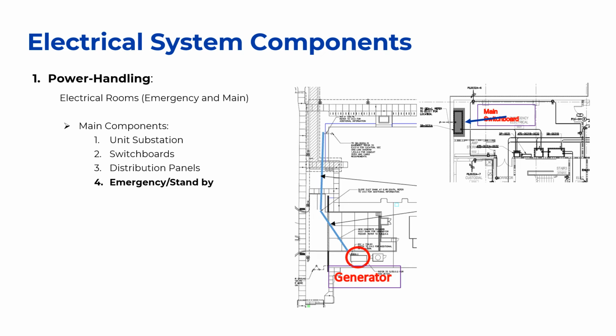Lastly, for power handling, there are the emergency and standby systems. These use either of two systems: an engine generator set or battery equipment. For the ECE building, the system used is the engine generator, a diesel set system where a generator is connected to a main switchboard in the emergency electrical room and runs on diesel. An important note is that the diesel generator has a concrete pad that must be designed and poured on site prior to the room being built.